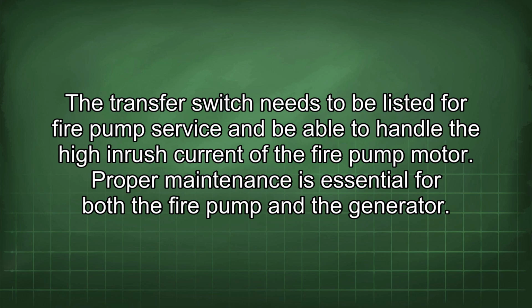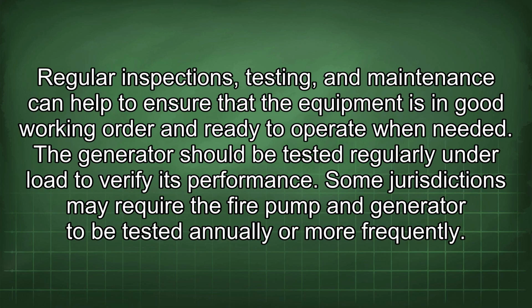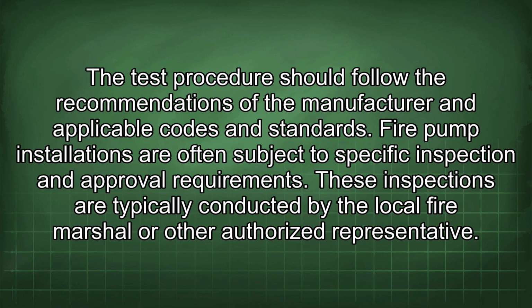Proper maintenance is essential for both the fire pump and the generator. Regular inspections, testing, and maintenance can help to ensure that the equipment is in good working order and ready to operate when needed. The generator should be tested regularly under load to verify its performance. Some jurisdictions may require the fire pump and generator to be tested annually or more frequently. The test procedure should follow the recommendations of the manufacturer and applicable codes and standards.